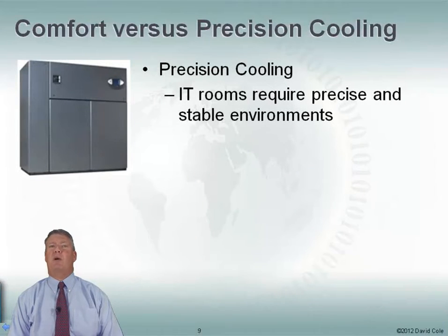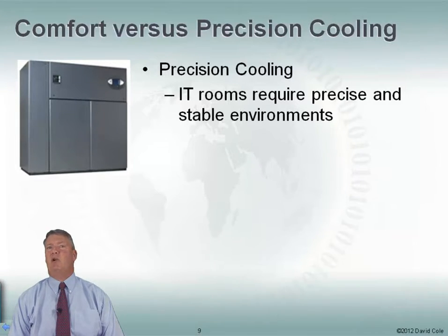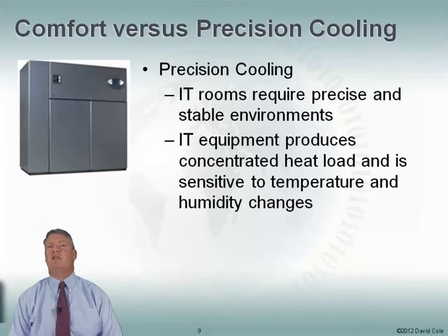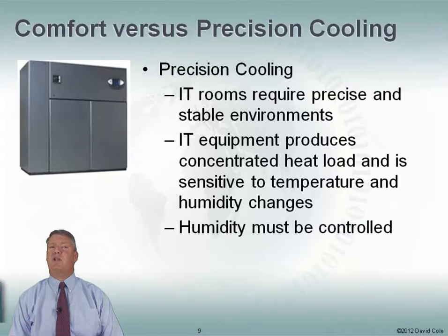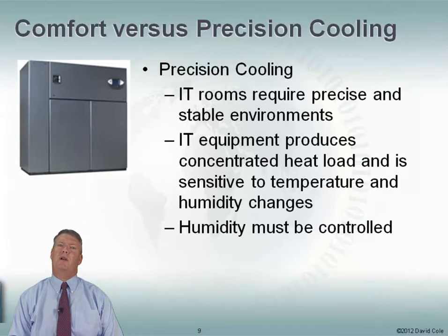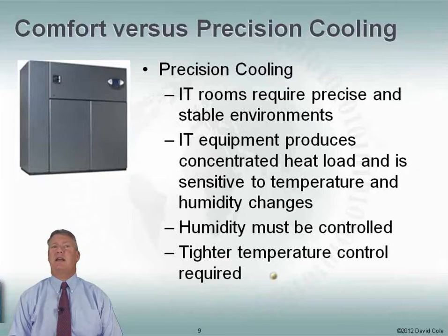Precision cooling — IT rooms require a precise, stable environment. It's important that we don't have big temperature swings and humidity swings when we're looking at servers, routers, and other IT equipment. IT equipment also produces very concentrated heat loads that are very sensitive to temperature and humidity changes. We have to control humidity. We don't think about humidity control very much when we're looking at comfort cooling, but in a data center the humidity must be controlled — we need tighter controls over both humidity and temperature.